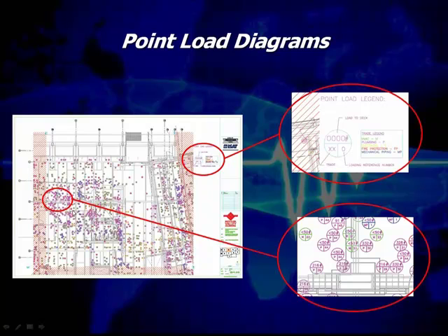And so this is a total map showing where all of those connections are made and what the loading conditions are, and it's specifically for the structural engineer to check the structure to verify that the structure is not overloaded. He'll come into some of these dense areas and look at those loads and verify that the deck is not overloaded on the project.